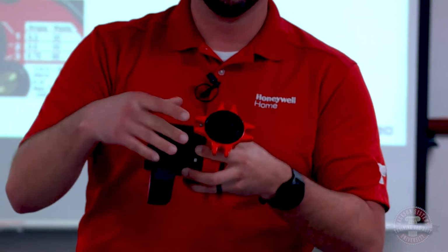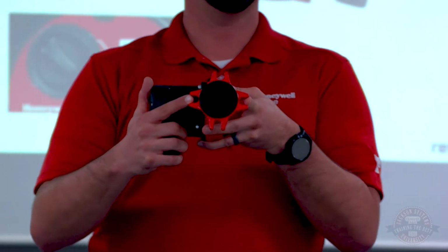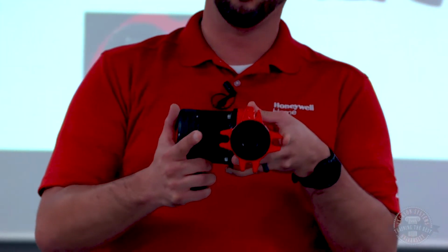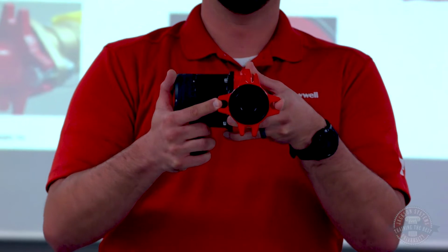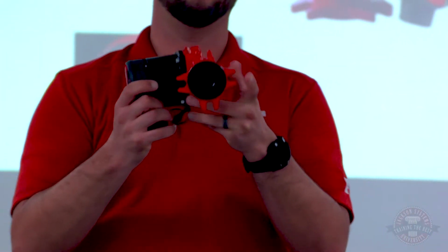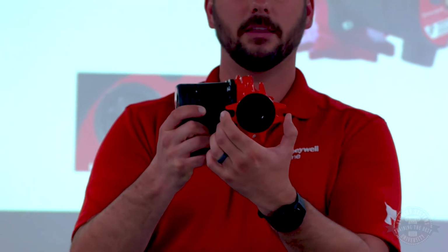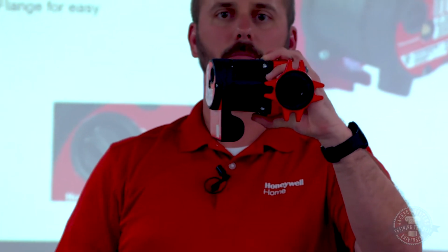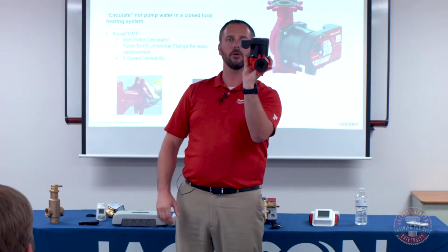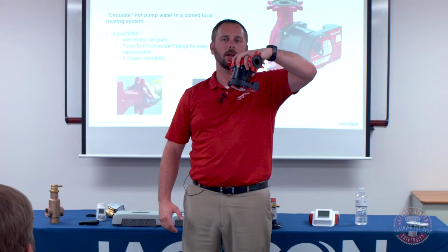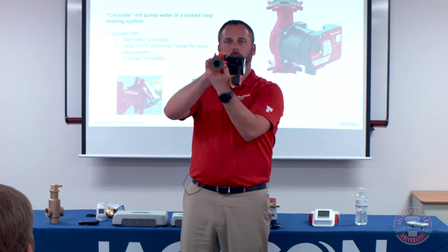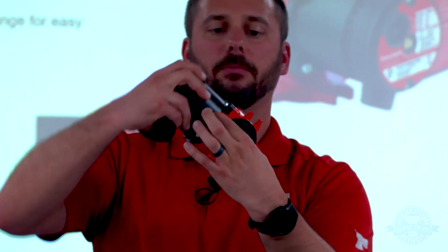The other thing that we have done is you'll notice that there are 4 bolts here. For those of you that do a lot of circulators, you'll know that your pumps are typically 2-bolt flanges. This does not require a special flange. So what we've done is we've actually just created 2 flanges inside of one. When you install a circulator, you have to keep the motor parallel to the ground. You never want to see the motor staring up at the ceiling. You never want to see the motor staring down at the ground. So it's always got to be at least parallel to the ground. So if you're ripping out a pump, let's say we only had 2 bolts here, it is possible you may have to mount the pump like this or unsweat those flanges and reattach it. With ours, it's going to go right in. Doesn't matter what you're replacing, if it's a rotated flange pump or not.